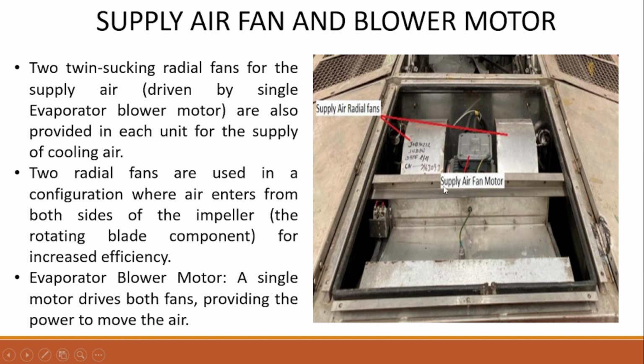Supply air fan and blower motor. Two twin-suction radial fans for the supply air are also provided in each unit for the supply of cooling air. The two radial fans are used in a configuration where air enters from both sides of the impeller for increased efficiency. The evaporator blower motor, which is a single motor, drives both fans, providing the power to move the air.